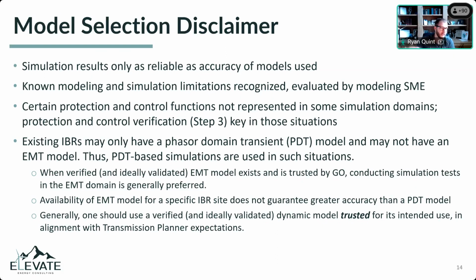They may possibly have that EMT model once Mod 26-2 goes into effect, but that's years from now. So those models shouldn't be expected to be readily available. It's very expensive and time consuming to get those models for existing sites, working with the OEMs, etc. So we just have to have some practical balance there. Really the document is saying use the best trusted model that you have that is ready for its intended use, and typically they need work regardless.